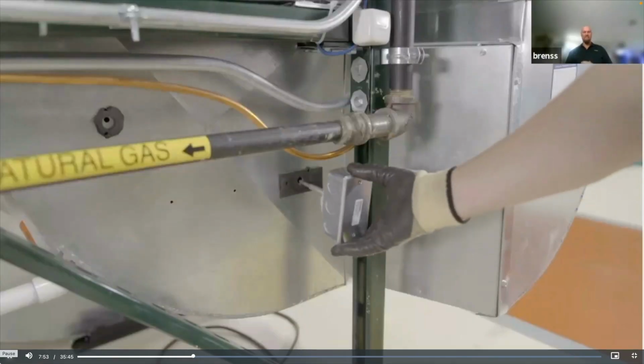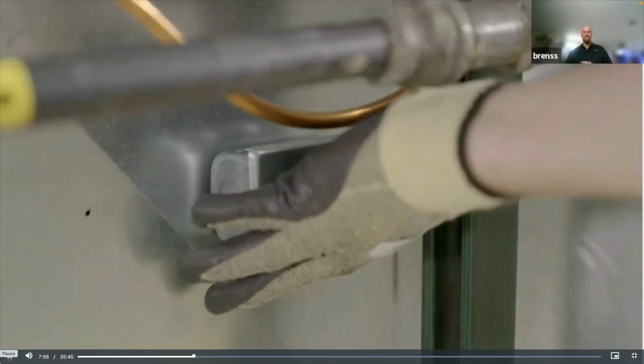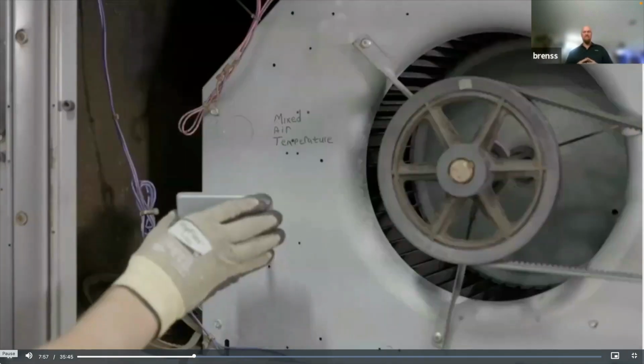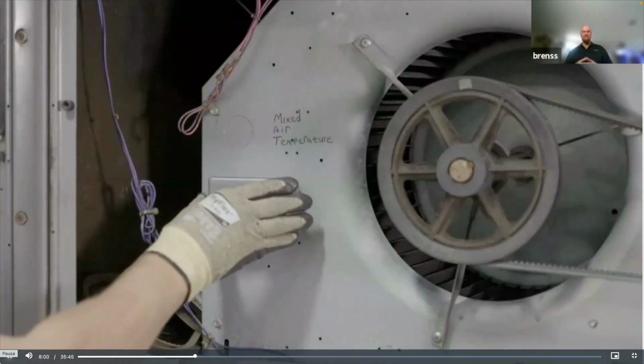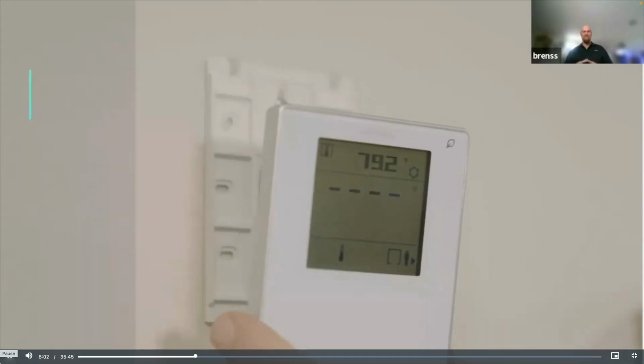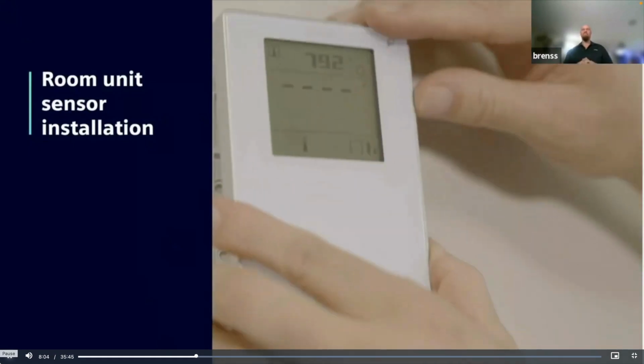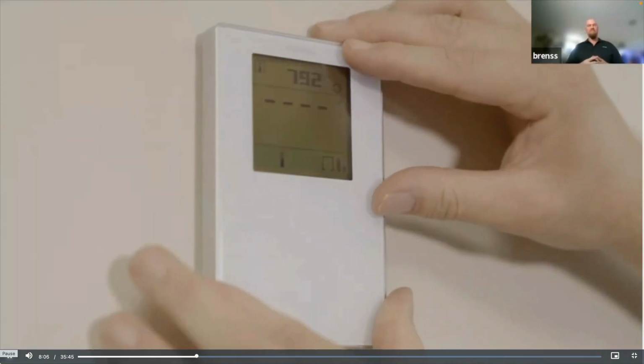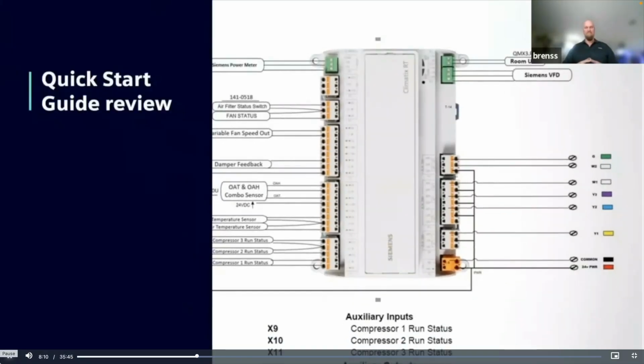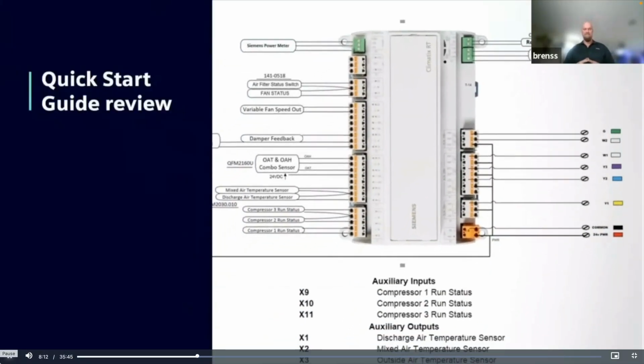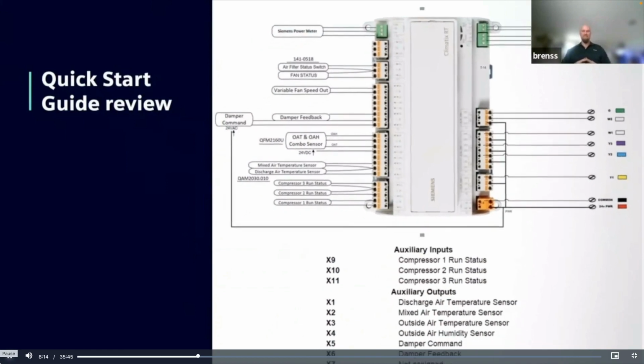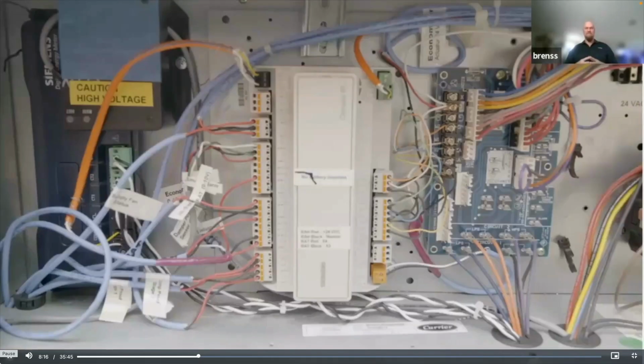The 10K temperature sensors are mounted on the air supply for discharge air and on the fan to sense the mixed air. The room unit sensor is mounted indoors. Refer to the Quick Start Guide for terminating the sensors at the Climatix controller and compare it to the actual unit.